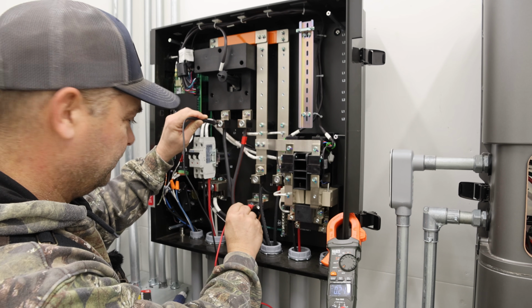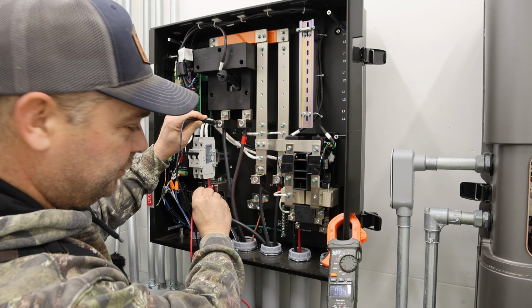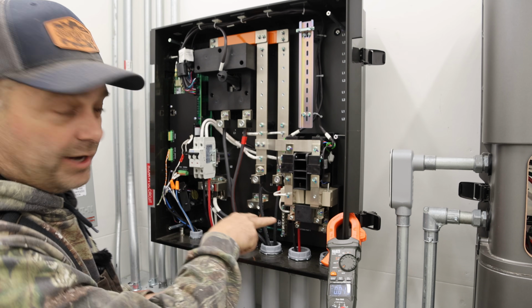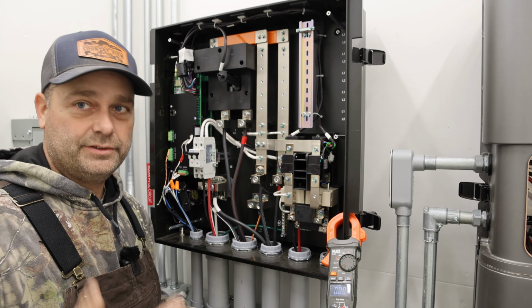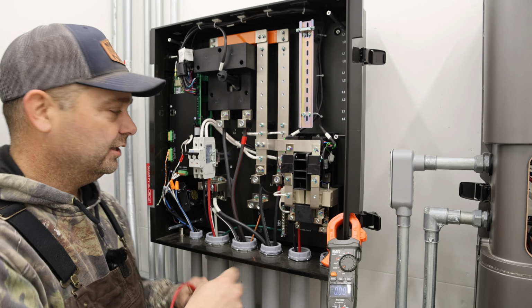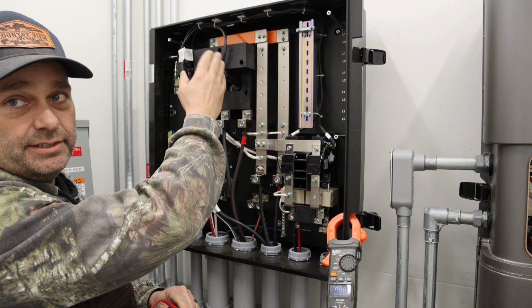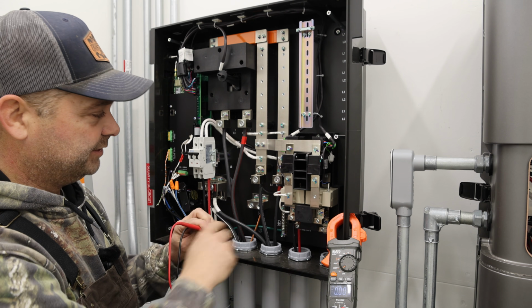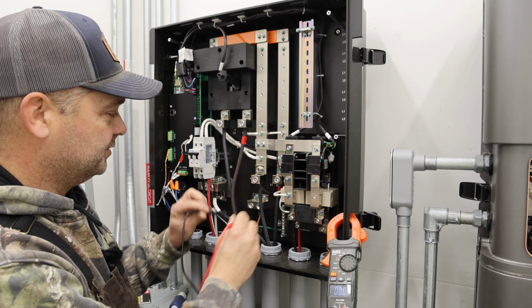All right, so we'll check our incoming power. Nothing there. We'll check at the ground, check at the neutral. And then we're going to check our outgoing power to make sure we're not having somehow power backfeed into the system. This is a disconnect. It's probably opened up, so these probably aren't connected, so we definitely need to check both sides of the circuit.